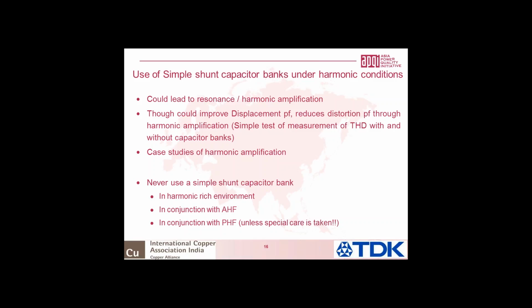Also a caution: whenever you're using a simple shunt capacitor bank with an active harmonic filter, it's not to be done at all. Even using a simple shunt capacitor bank with a tuned harmonic filter, I would not recommend it, but it can be done provided you have an expert looking at it, because there could again be some parallel resonances where it could create a lot of open circuits.